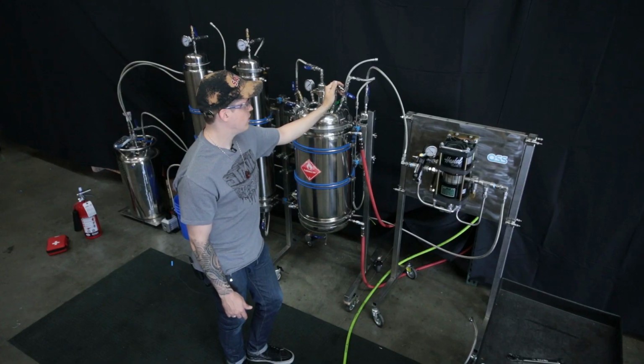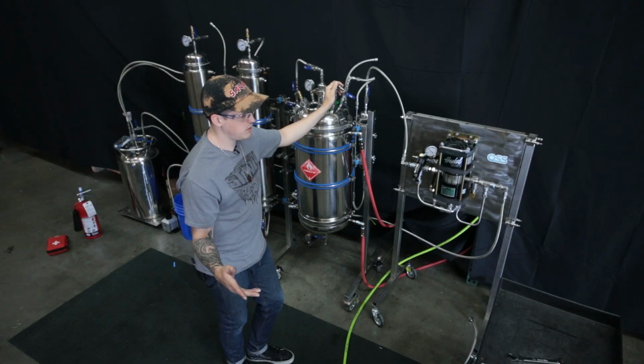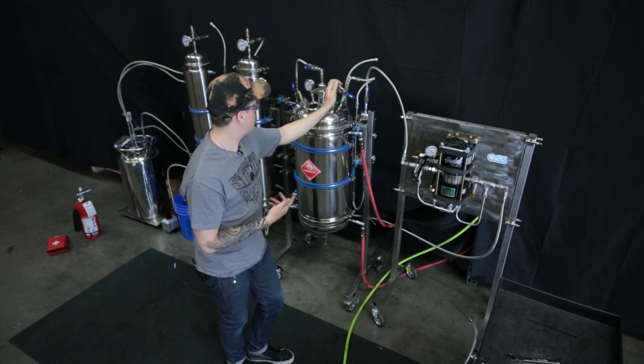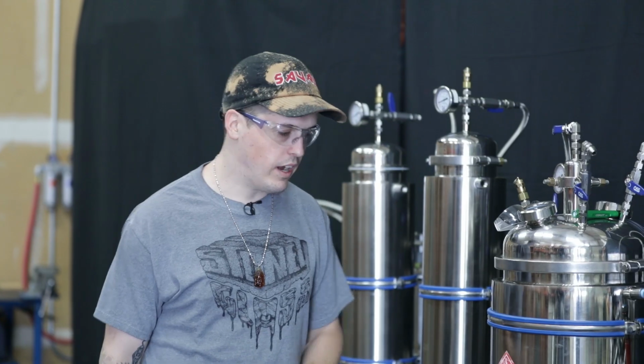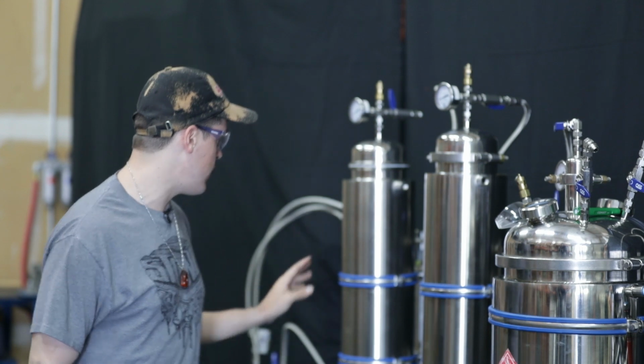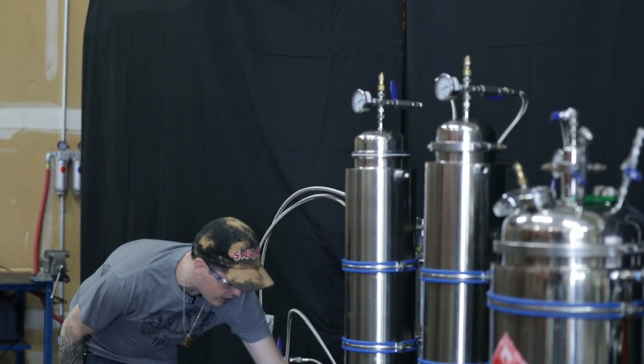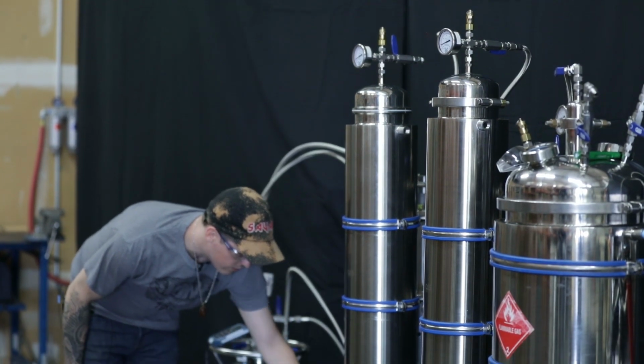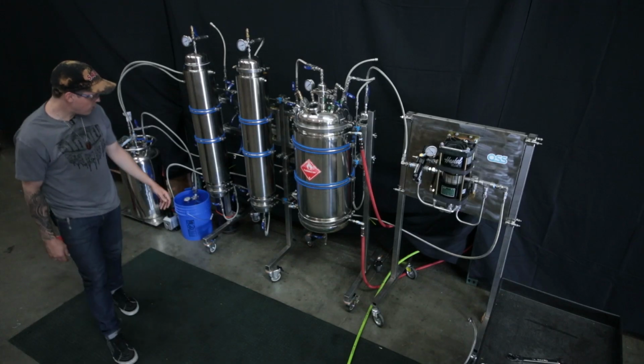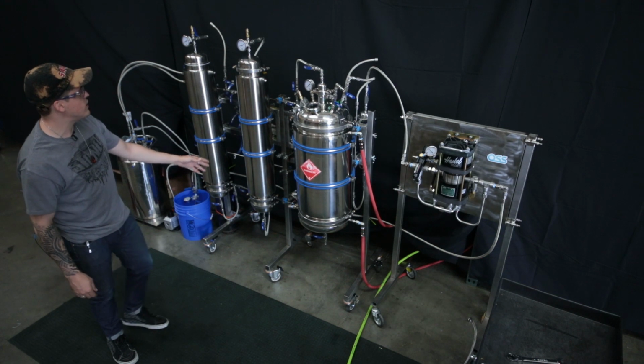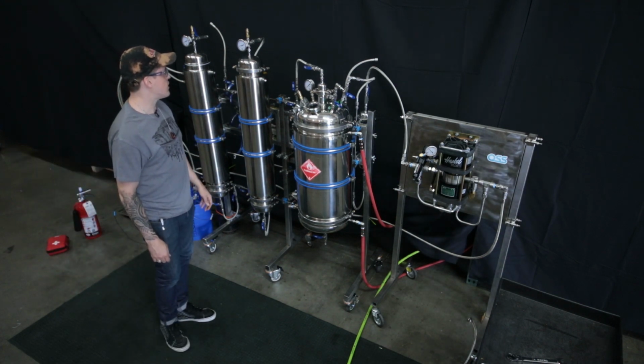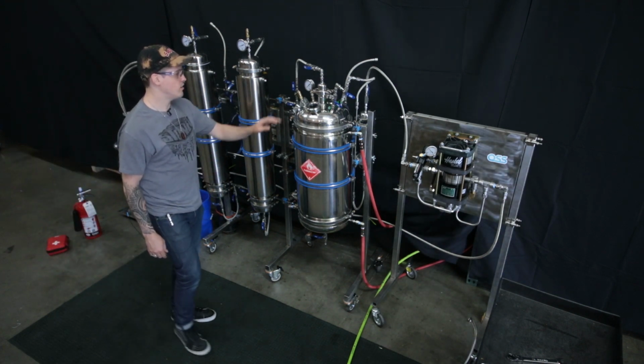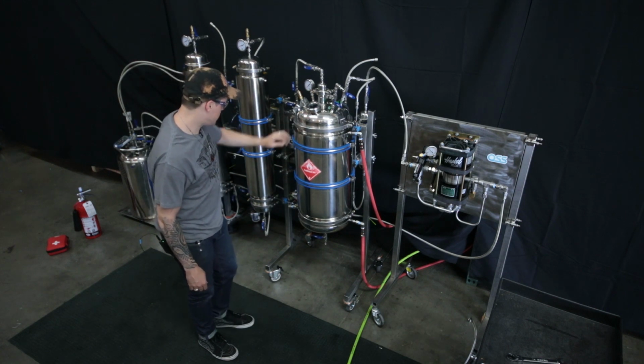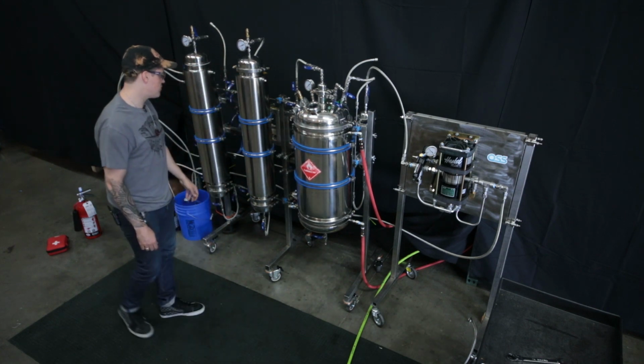So once we reset back to 0, which is essentially now, we'll close off the valve. I'm going to go ahead and hook up my vacuum, which I have already connected to the system down here. I'm going to flip it on and open up my valve to the system. And then I'm going to go over here and make sure that it's pulling a vacuum on all of the vessels that I'm going to be using today, so the evaporation vessel and this column full of material.